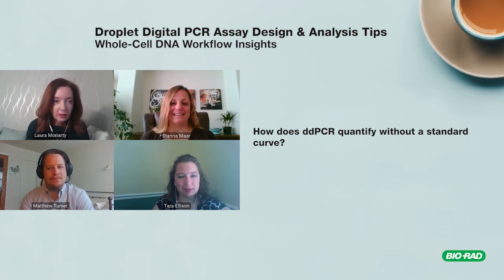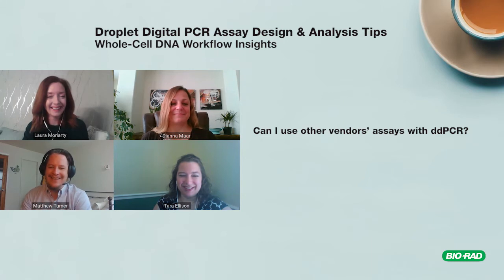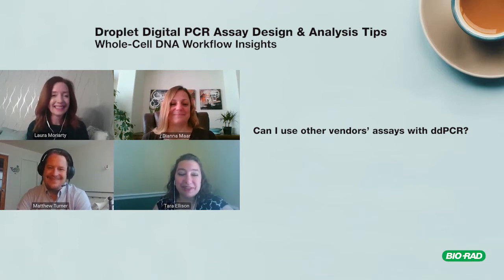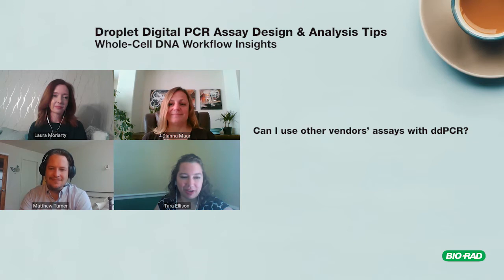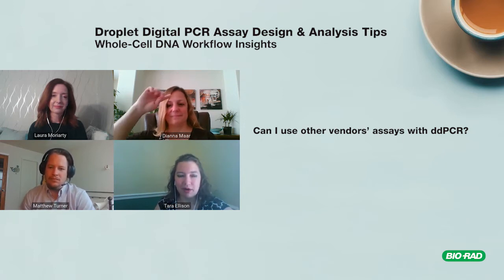Question: can this person use other vendors' assays with ddPCR? Matt: The short answer is yes — it is not a locked system. If you have a qPCR assay that measures what you're interested in, chances are you can port that assay pretty much directly over to digital PCR. There may be a little optimization needed sometimes, but not always. The QX200 is a two-color instrument: channel one for FAM-labeled probes, channel two for HEX or VIC labeled probes, and we also have EvaGreen chemistry compatible with primers alone.